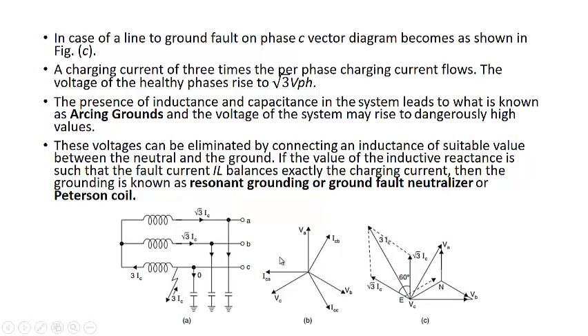One more thing that we need to understand is that this current, 3 times IC, even if it is a fault current, its value is very small, and in protective relaying it is not usually detected by the relay, because the load current will still be greater than this current, 3 times IC. Differentiating this current from the load current will be difficult for us, and so it will not be detected. A single line to ground fault in an isolated neutral system will not be detected. In the ideal case, you will see this 3 times IC will also be equal to 0, because practically there is an open circuit between phase A and ground, so there will be no current.